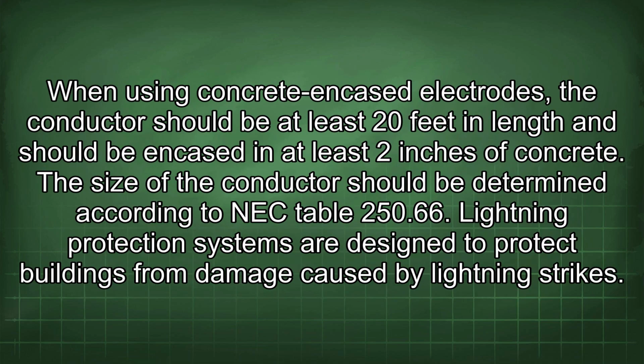When using concrete encased electrodes, the conductor should be at least 20 feet in length and should be encased in at least 2 inches of concrete. The size of the conductor should be determined according to NEC Table 250.66.